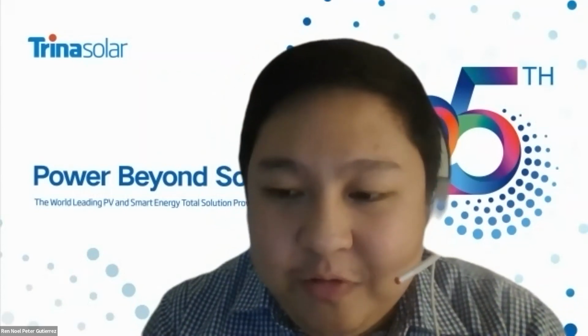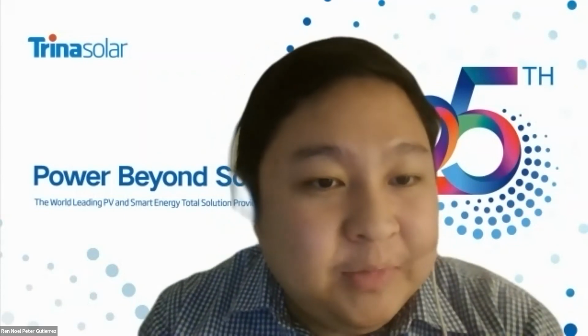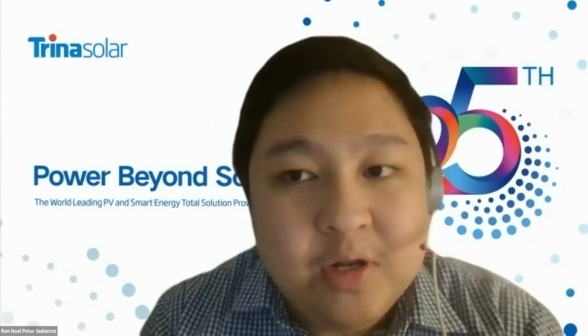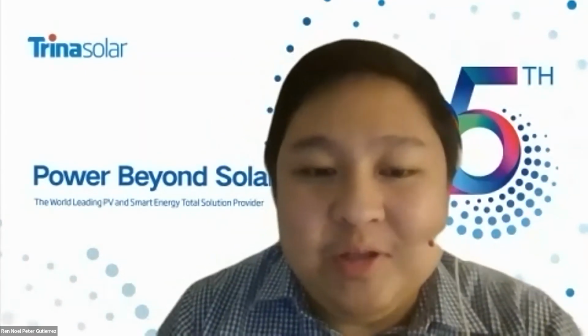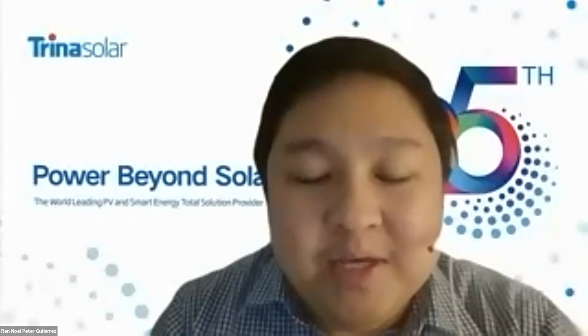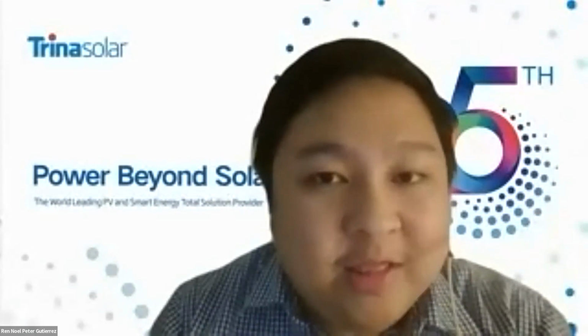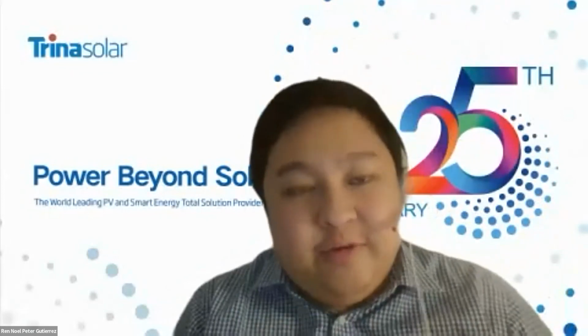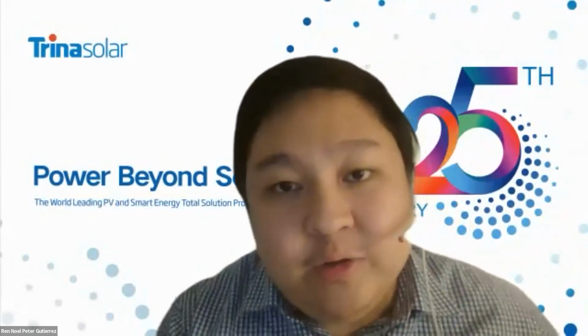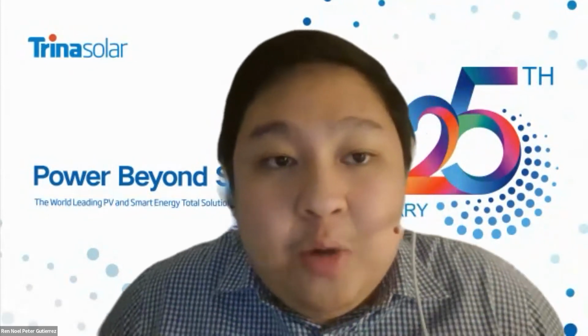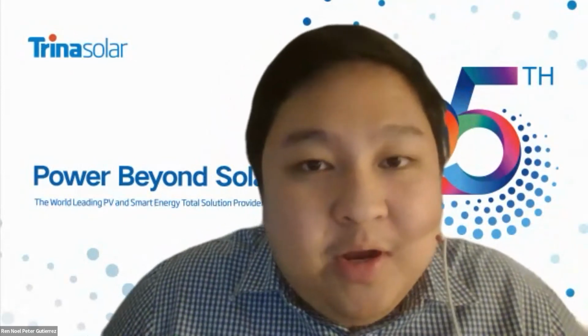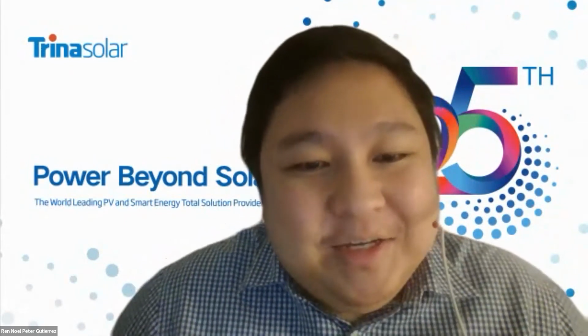That's very important. Second, in the Philippines there is a requirement for rapid shutdown already. This rapid shutdown is a tool, I think, especially for C&I rooftop projects. This is a requirement in the Philippine Electrical Code. So this rapid shutdown can help avoid such kind of fire, or if a fire starts, it will not spread out immediately. There's another layer of protection, so it can save the rest of the system as well, and maybe the rest of your building or your houses.